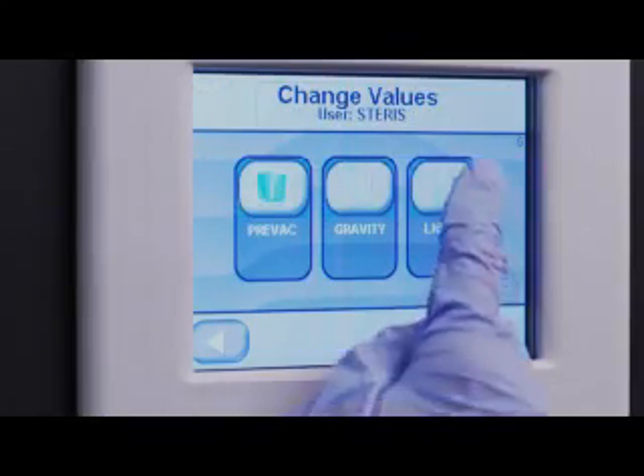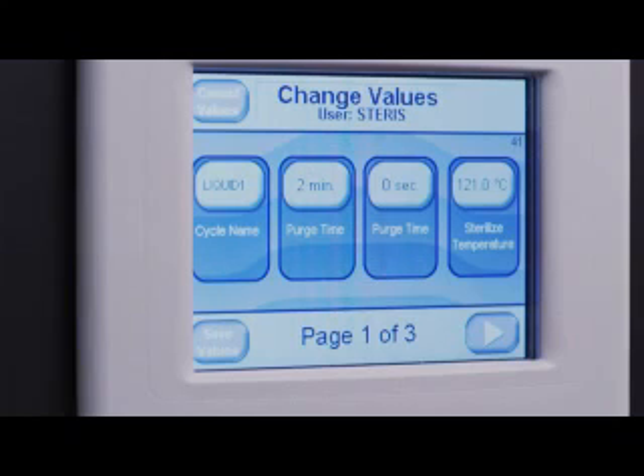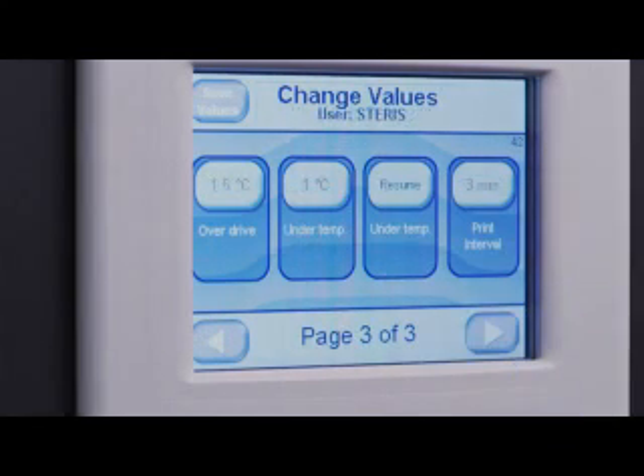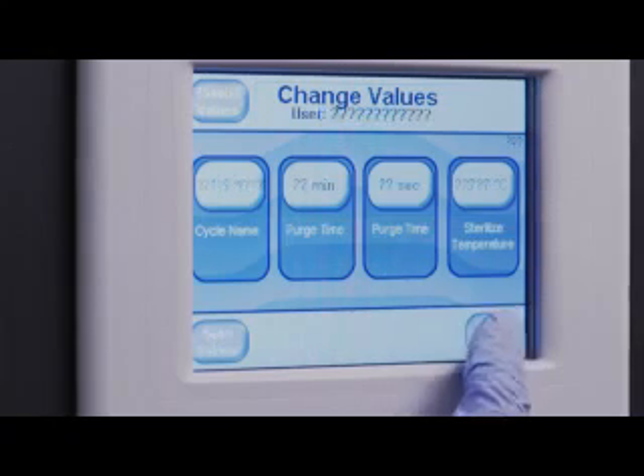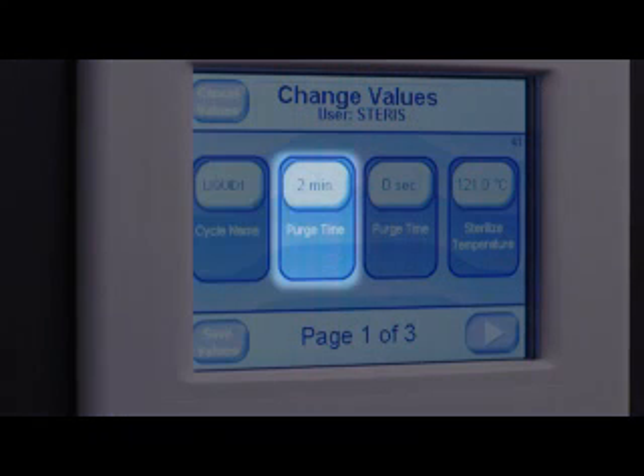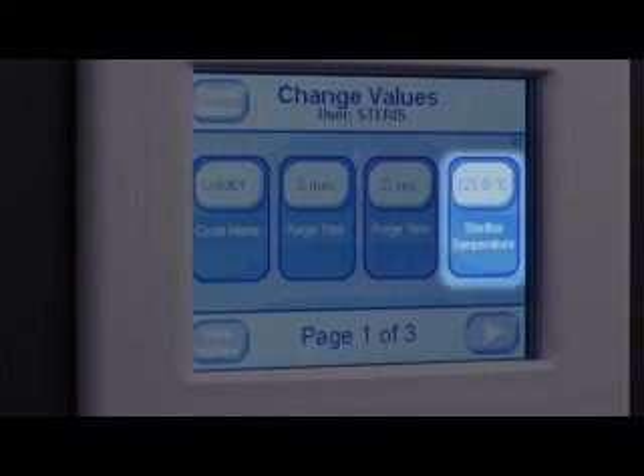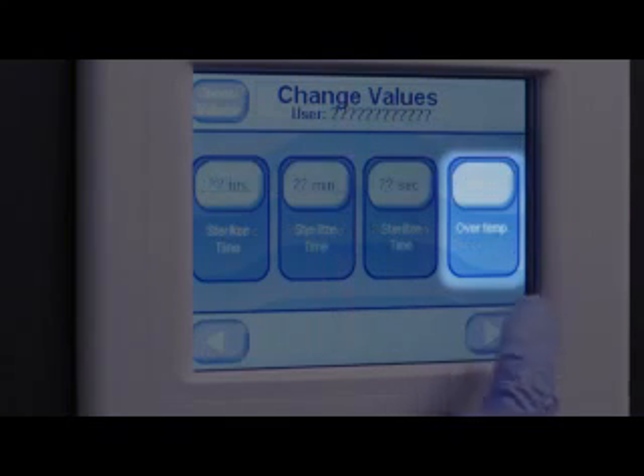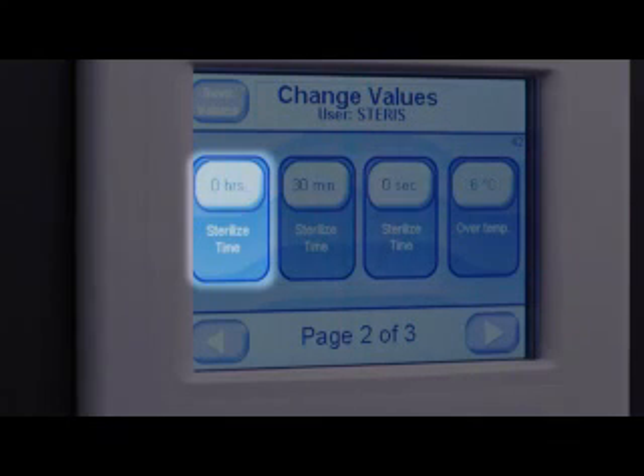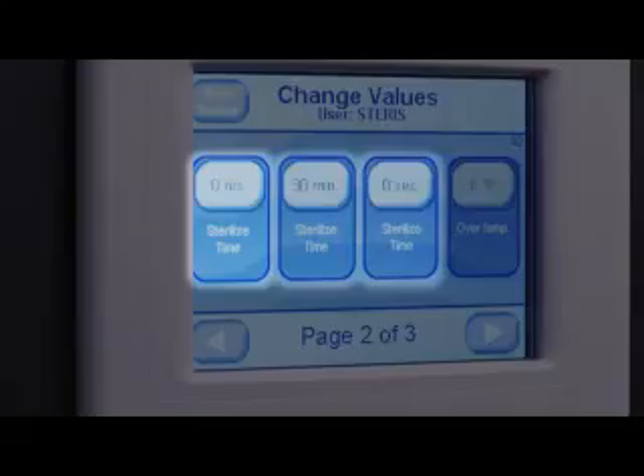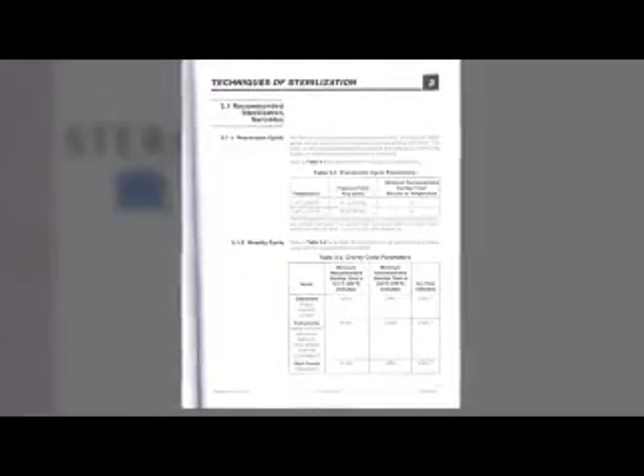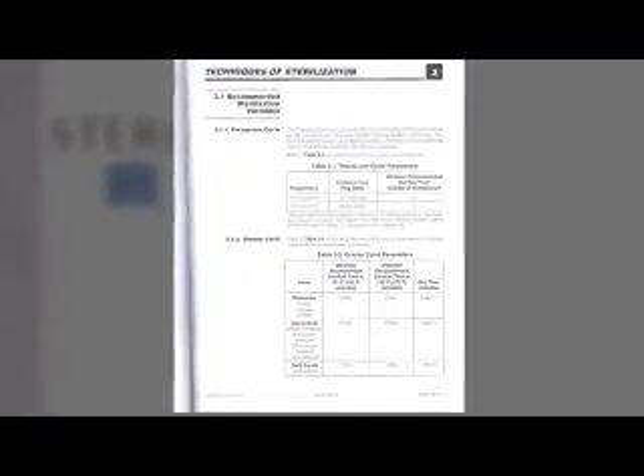Start by choosing a program to modify, and then choose the type of cycle you wish to use. Remember, if you are sterilizing media or other liquids, to only utilize the liquid cycle. From here, you can name the cycle, adjust the purge time in minutes and seconds, set the temperature for the sterilization phase, along with the time in hours, minutes, and seconds. For guidelines concerning proper cycle parameters, please consult your operator manual for the section on techniques of sterilization in Section 3.